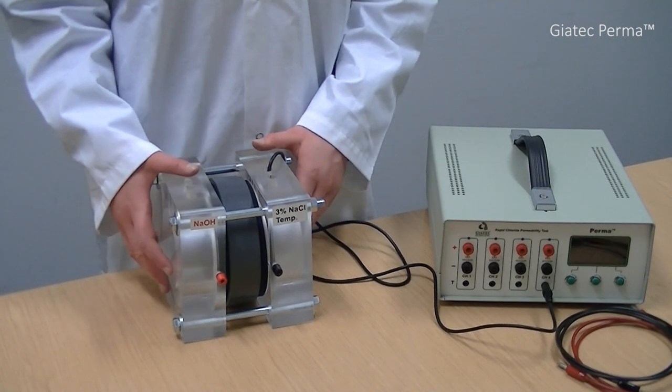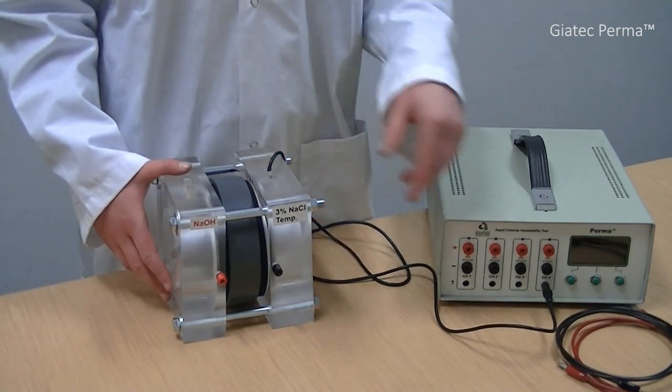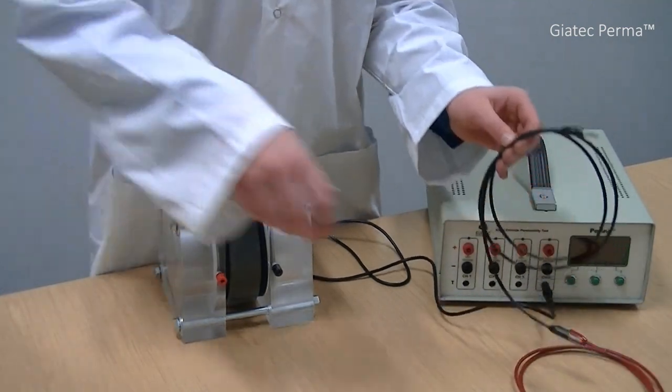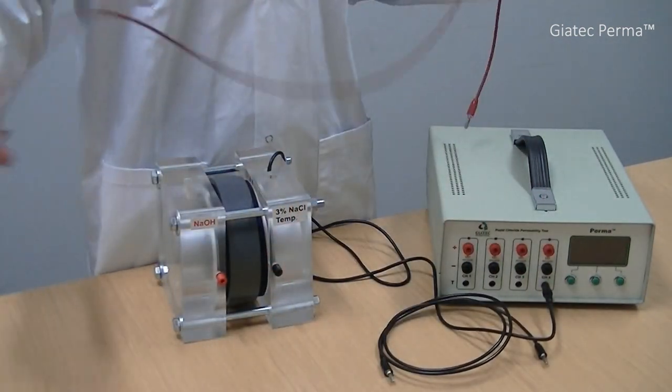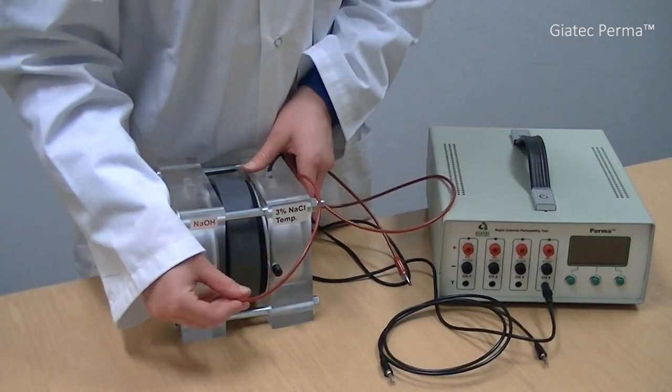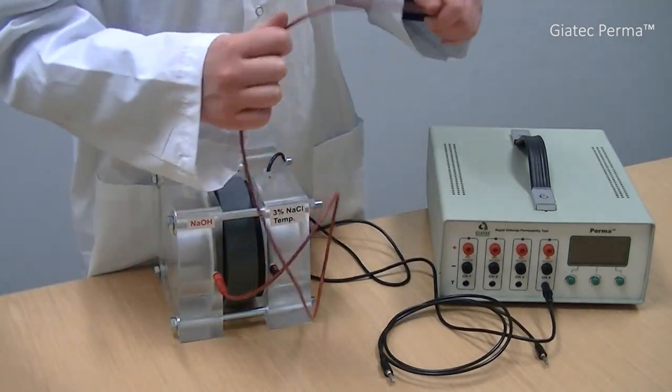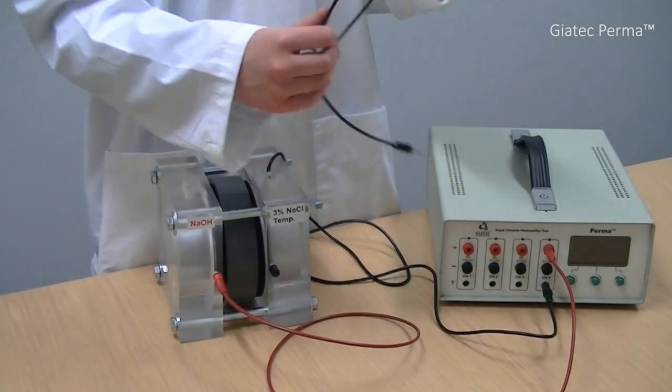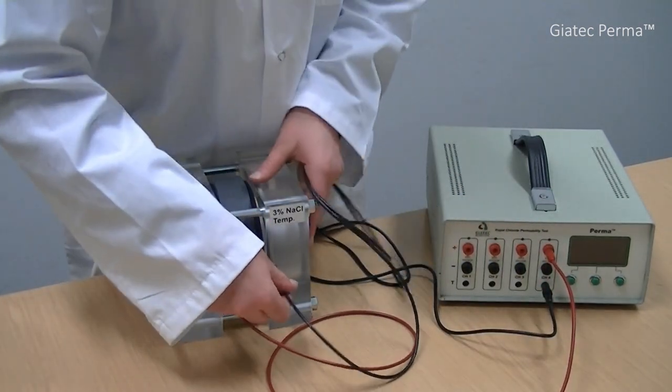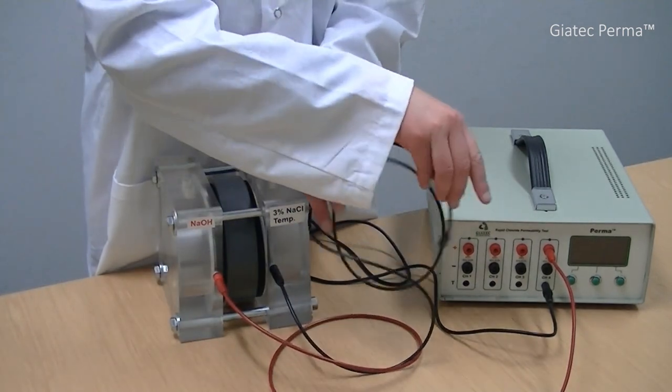Then, the test cell needs to be connected to the terminals on the device using the red and the black cables. I connect the red cable to the red jack of the cell and the red jack of the device. And then I connect the black cable to the black jack of the cell and the black jack of the device.